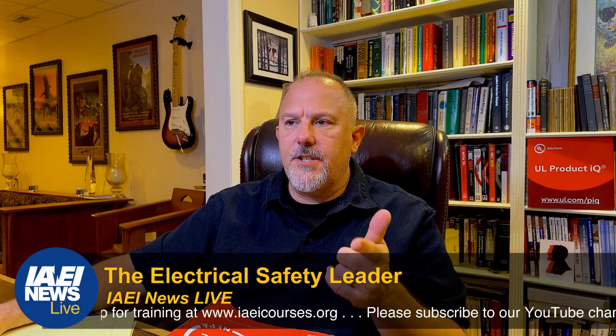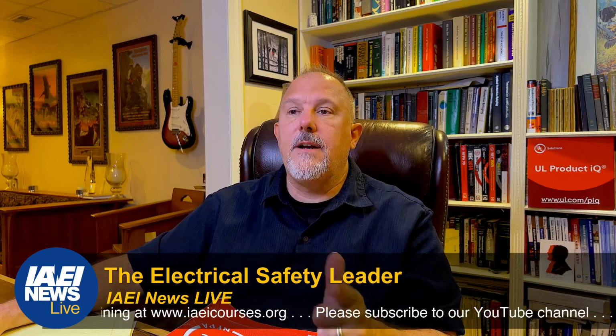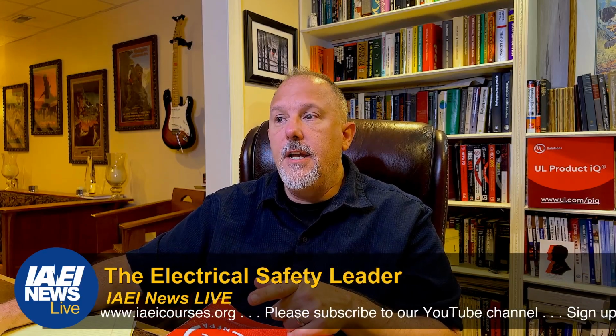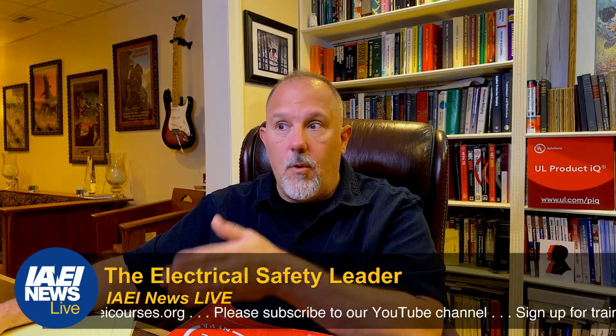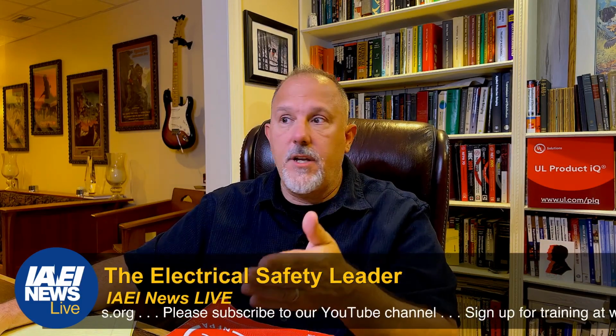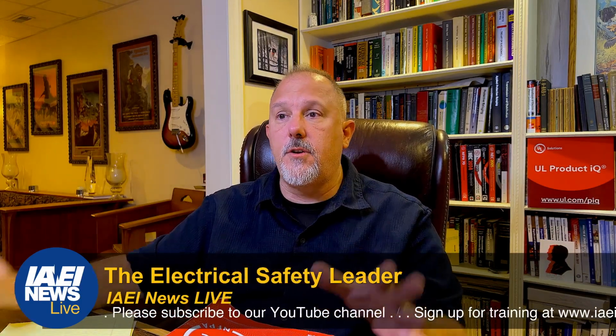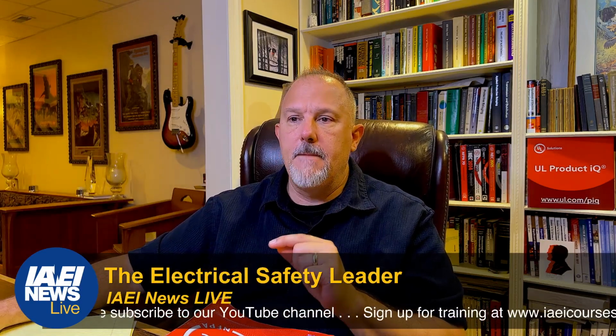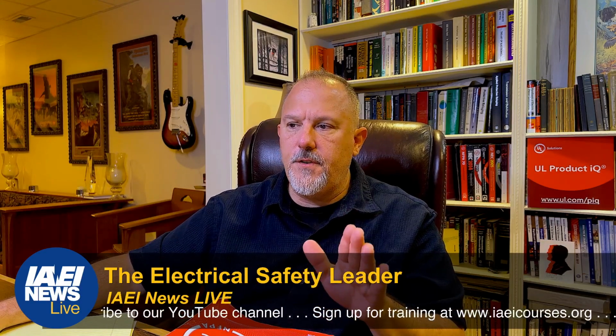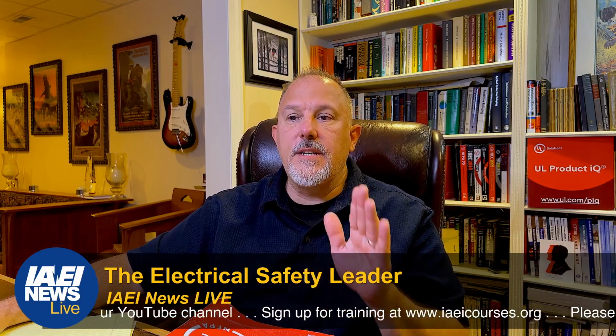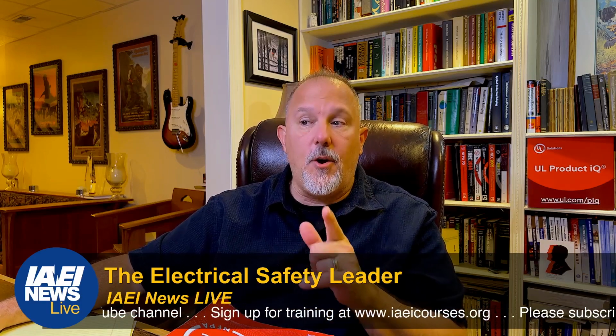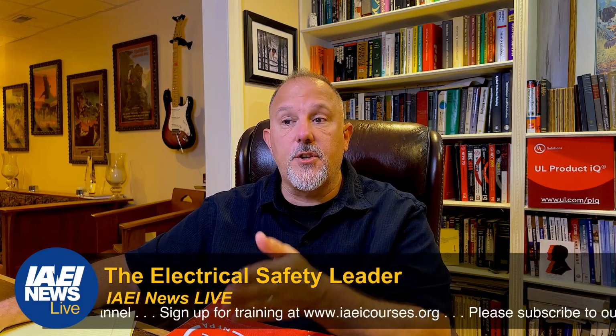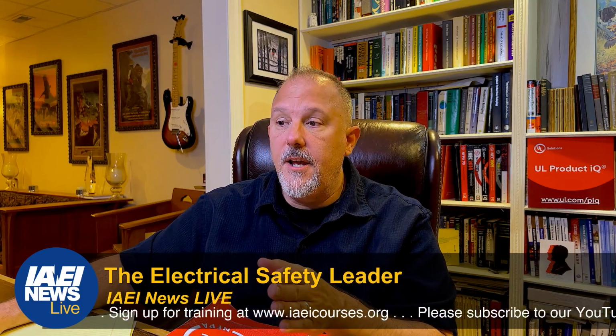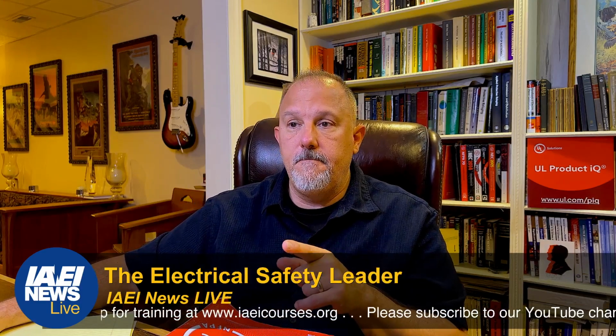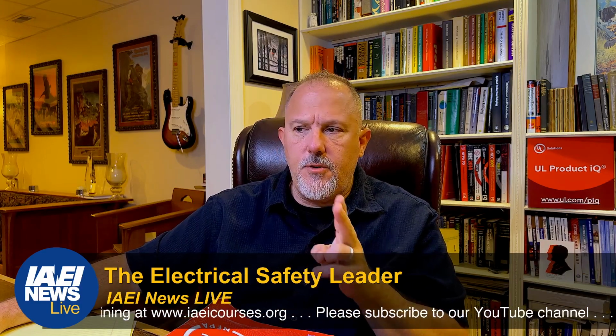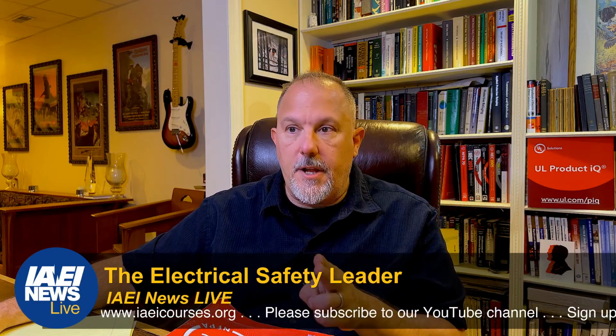There's a surge arrestor. And now in 502, it tells us surge arresters and surge protective devices installed in Class 2 Division 1 locations have to be in suitable enclosures. So that doesn't help us. I'm staying out of 242 because we went through 242. 501, Class 1: surge arresters and surge protective devices shall be non-arcing. So this is in Class 1 Division 2. In 501.35(B), there are some additional requirements. And here we go. There are only two other places in Article 230.